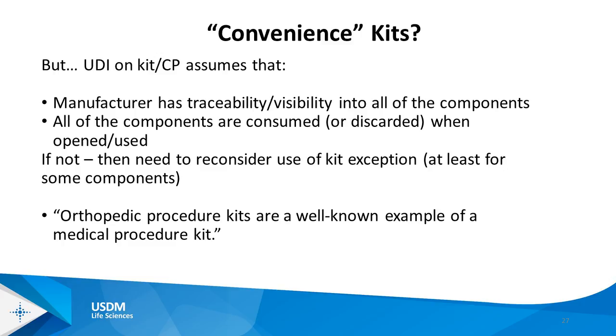So UDI on a kit is sufficient to provide the identification and support the traceability of that kit over its entire life cycle. The manufacturer knows what went into that kit, so if somebody needed to recall a component, they would know which of the kits had that recalled component in it. If someone needed to report a problem, they opened up the kit, something was missing or broken or what have you, they would have the UDI of the kit right there available. If your kit does not work that way, if the components are not consumed or discarded within that one event, the opening of that kit, if these components have a life outside that kit, then you need to reconsider the use of the kit exception and the identification of the components within that kit.